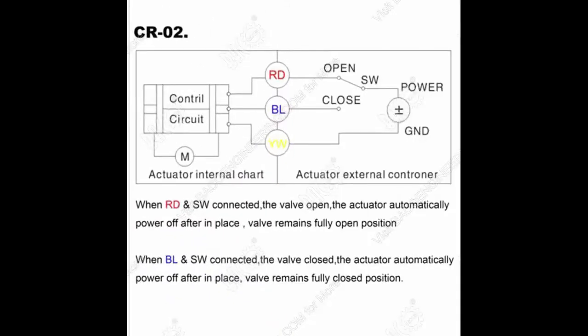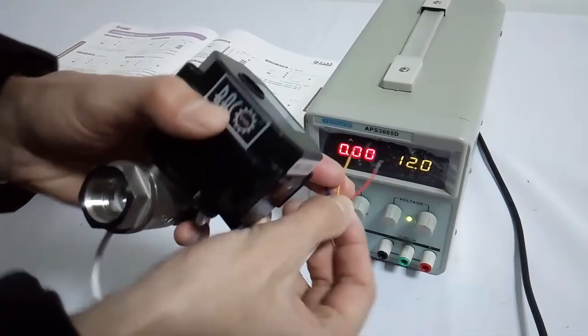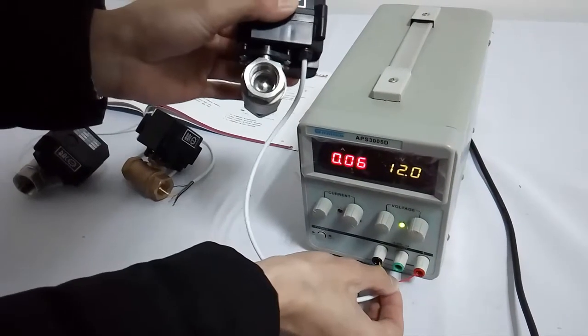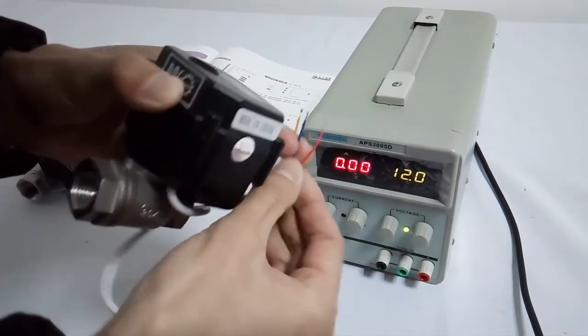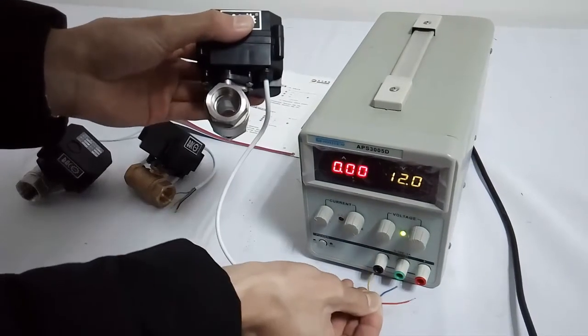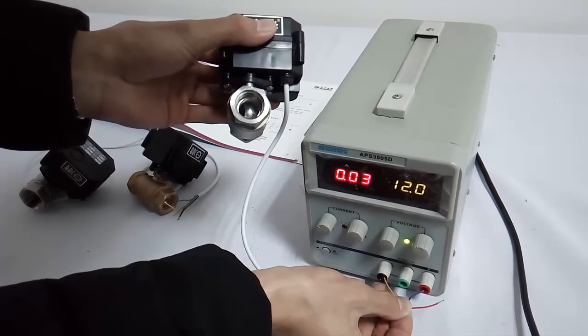Wiring diagram CR-02: It has 3 wires — red, blue, and yellow. When red is connected to the positive pole and yellow is connected to the negative pole, the valve will be opened fully. Power off automatically after in place. When blue is connected to the positive pole and yellow is connected to the negative pole, the valve will be closed fully. Power off automatically after in place.